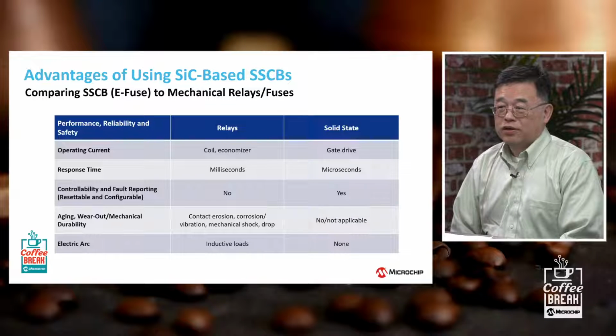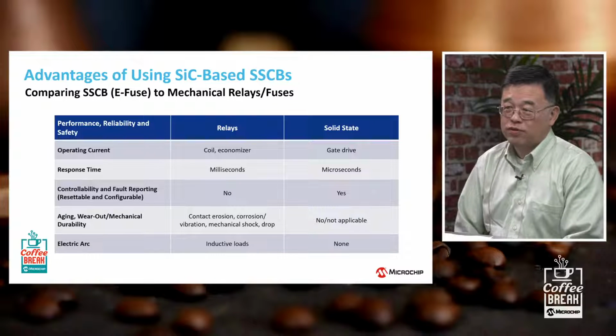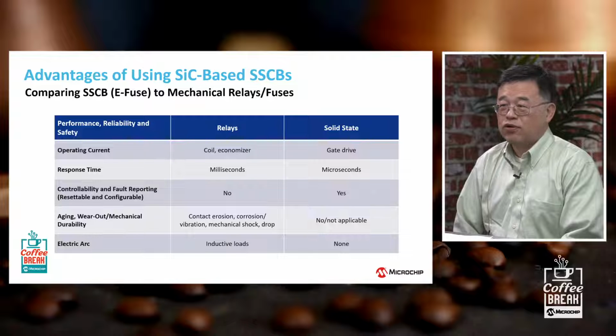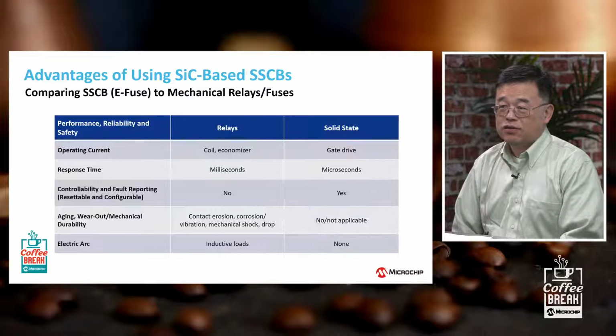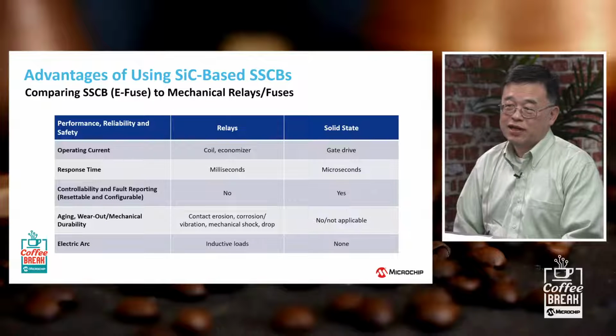Whereas an electronic circuit breaker, we call it E-fuse in Microchip terms, a solid-state circuit breaker, trips, and when it trips, it can be reset and controlled remotely. It doesn't have all the moving components, so it's actually quite reliable. You can place it in a more compact area away from a service bay, for example, giving you more flexibility in designing the circuit breaker rather than forcing it into an area where people need to access it to minimize equipment downtime.